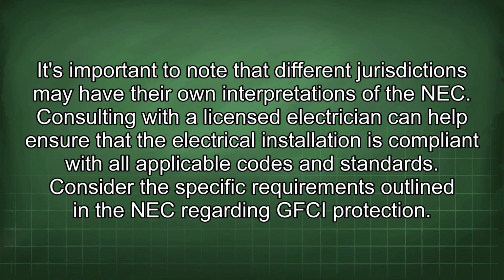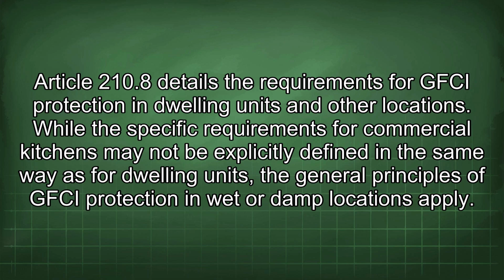It's important to note that different jurisdictions may have their own interpretations of the NEC. Consulting with a licensed electrician can help ensure that the electrical installation is compliant with all applicable codes and standards. Consider the specific requirements outlined in the NEC regarding GFCI protection. Article 210.8 details the requirements for GFCI protection in dwelling units and other locations. While the specific requirements for commercial kitchens may not be explicitly defined in the same way as for dwelling units, the general principles of GFCI protection in wet or damp locations apply.